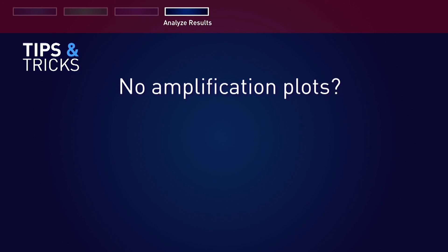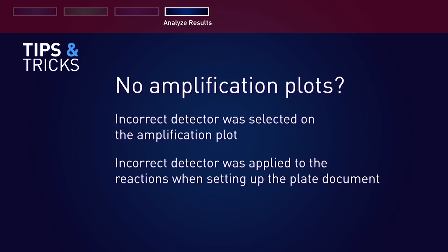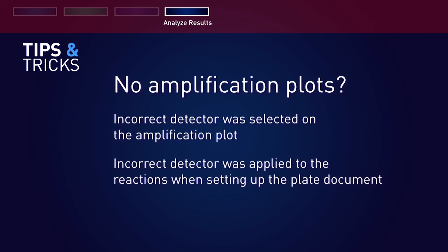If you find there are no defined amplification plots, it may be because an incorrect detector was selected on the amplification plot, or an incorrect detector was applied to the reactions when setting up the plate document.